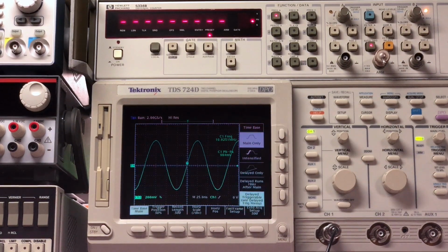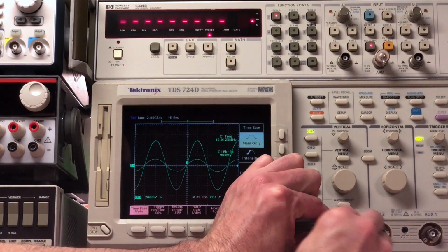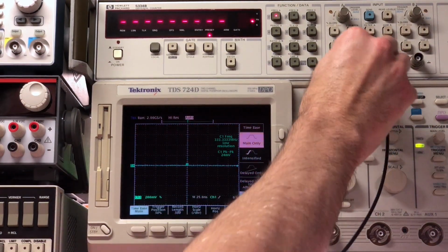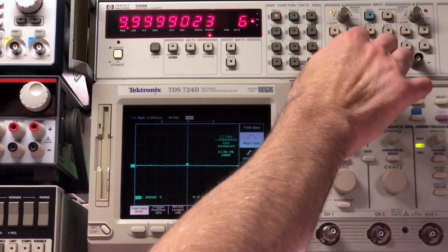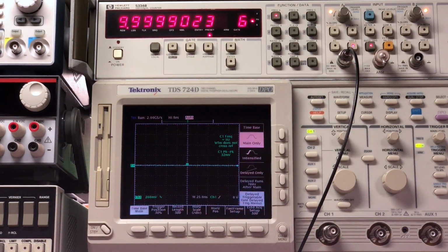All right, so again, back with the 50 ohm impedance there with the 50 ohm pass-through termination, and the waveform again looking very good, but let's take a look at the frequency on the frequency counter and see how close that is to 10 megahertz. So move this over and connect it up here. Now the frequency counter has a 50 ohm input. I need to select that right there. Okay, so we don't need that pass-through termination because again the termination inside the frequency counter is now set for 50 ohms.